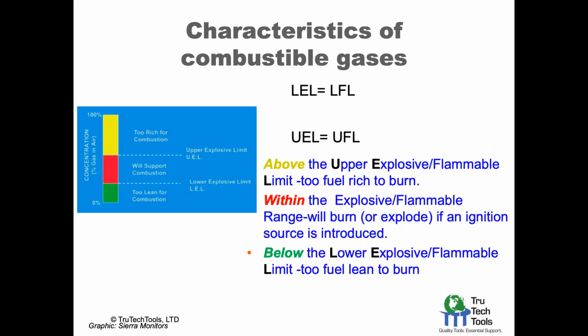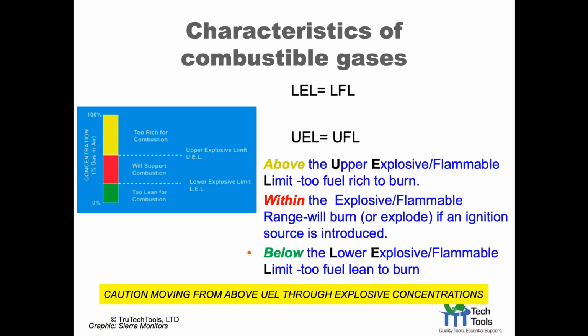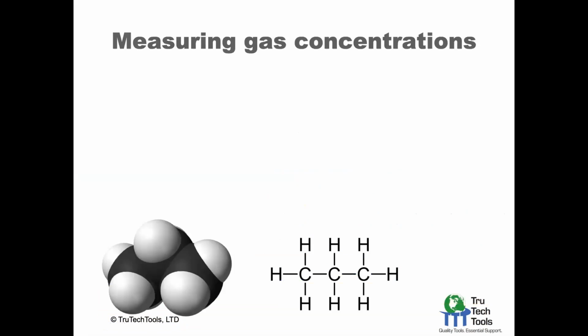The concern here is if you ever enter this range, which is why you want to actually take a measurement. If you ever enter the range where you're above the upper explosive limit, the UEL, and the air clears or it blends with fresh air, you'll move back through the combustible range. So that's why it's important to know these different limits and the concentrations. And we'll talk about the action level for BPI as we get into the standard. So again, there's caution when moving from the UEL: even though it's too rich to support combustion, when the air clears, you could get into a range where it will. So you've got to be very careful if you're ever above the upper explosive limit.